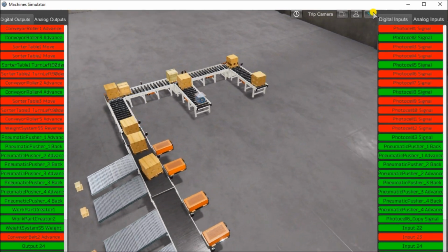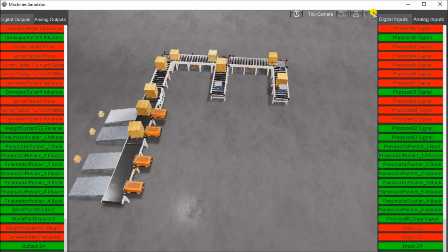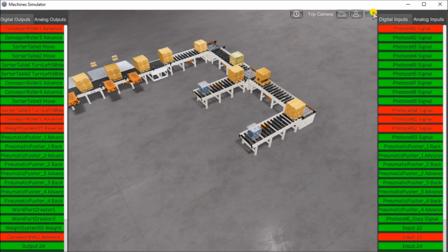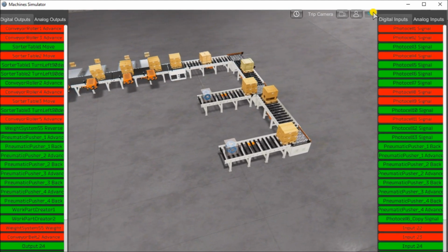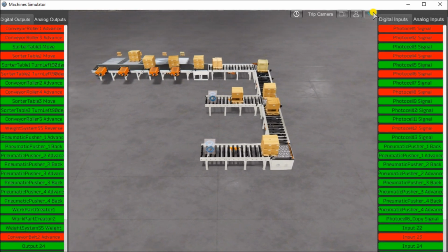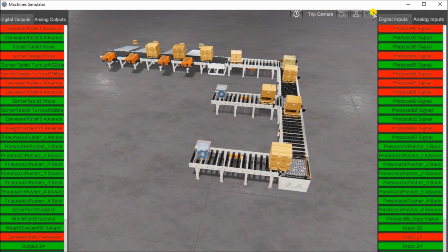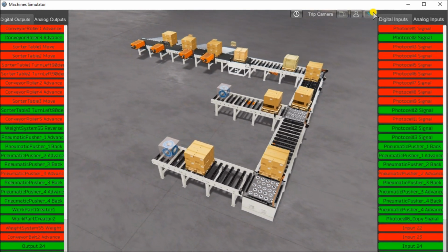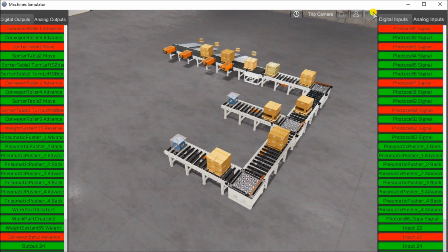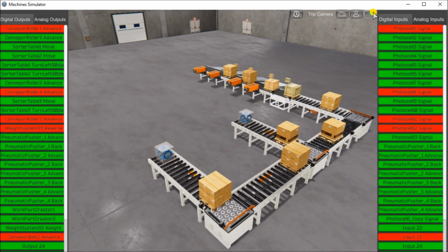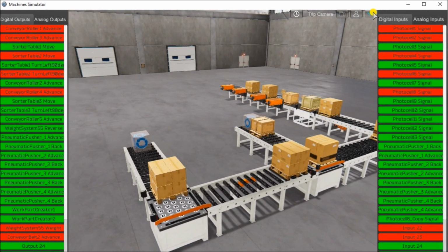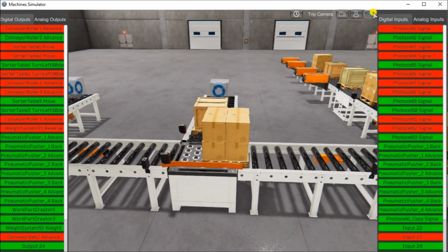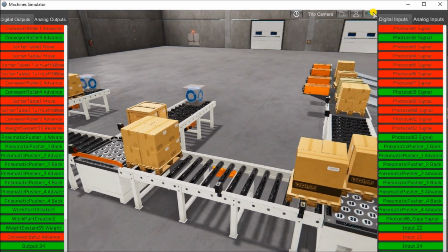And then PLC program testing is an important step to test all the conditions for the logic, like power cycle, sensors failing, safety, etc. So test the program with the simulator or actual machine. Make modifications as necessary and check with the people most knowledgeable on the machine to see if it's doing what they expect. And what I would do is after the program is commissioned, go back after a month or so and again ask, is everything working fine? Are we good to go? And is there anything else that we need to add in the program to make this more user-friendly?